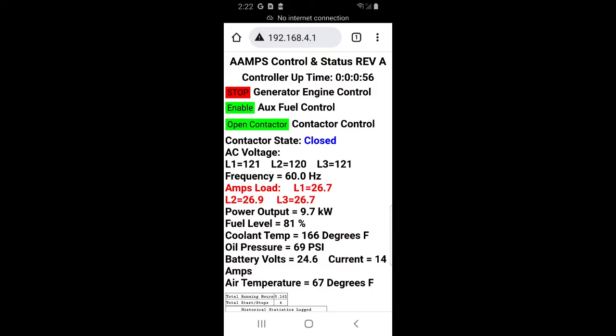Here is a sample of what the web page looks like when the generator has been started using Wi-Fi, showing the real-time parameters displayed. At the top are the generator controls for starting and stopping the generator, enable and disable of the auxiliary fuel system, and opening and closing of the contactor. The present state of the contactor is displayed as well as AC output voltage on each leg, the output frequency, the load current on each leg, the output power in kilowatts, the present fuel level, the coolant temperature, the oil pressure, the battery voltage and charge or discharge current, and the outside air temperature. If a parameter gets close to the generator's minimum or maximum limits, the parameter will be displayed in red as shown.